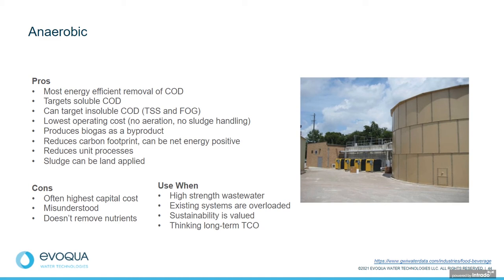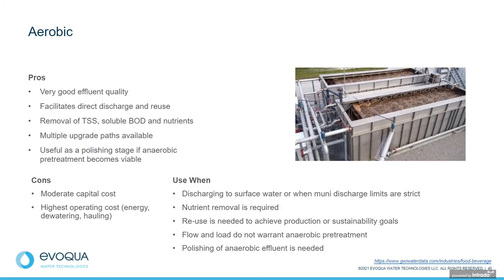So generally, when we see high-strength wastewaters, they're good candidates for anaerobic pretreatment, and then we'll add the aerobic polishing if needed. Aerobic, as I mentioned, has high operating costs but the best effluent quality. You will get your nutrients removal here. If you want to do direct discharge to a river, you need to have an aerobic system.